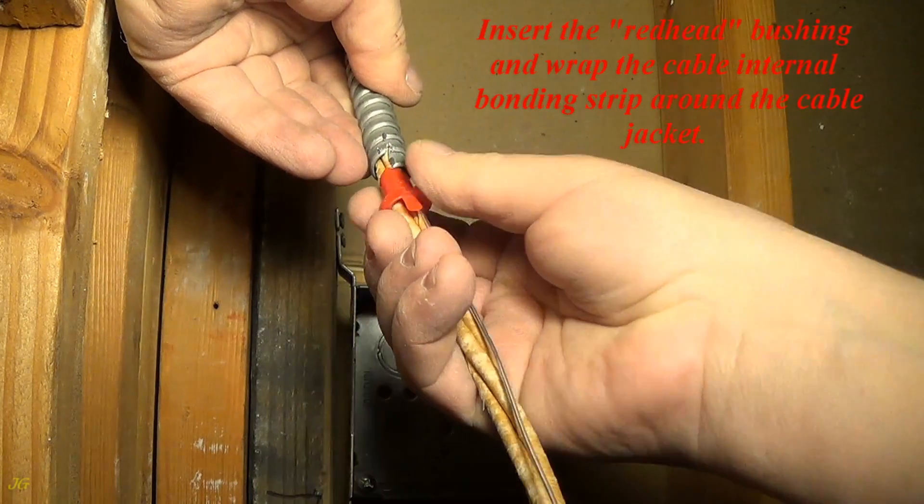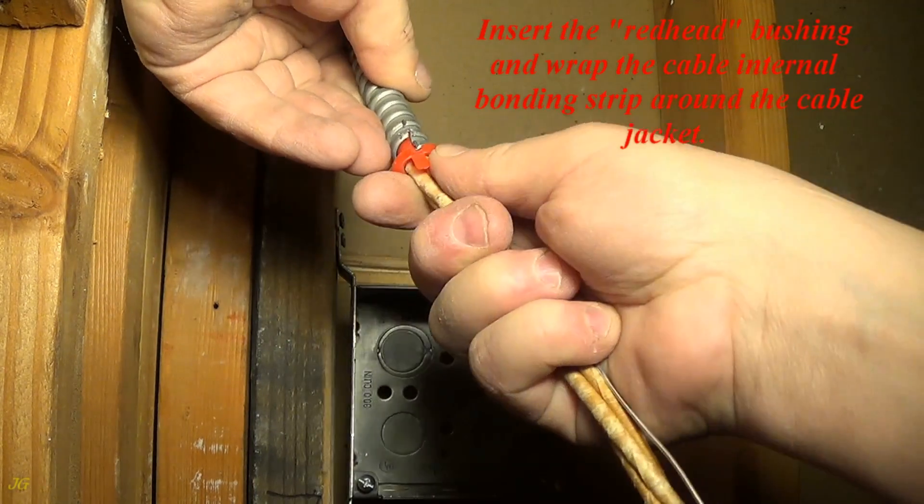Insert the redhead bushing and wrap the cable internal bonding strip around the cable jacket.